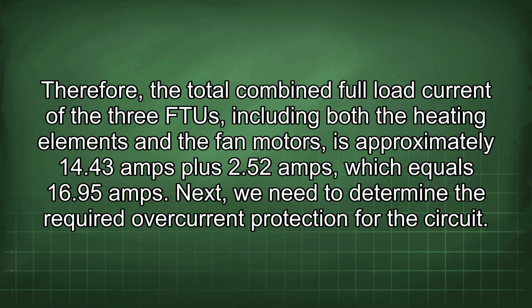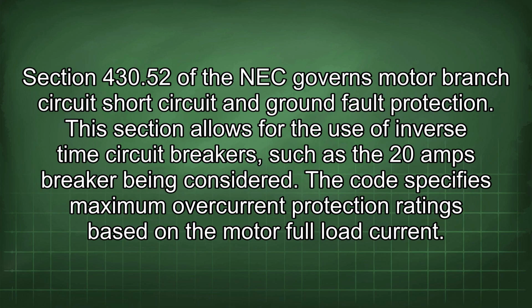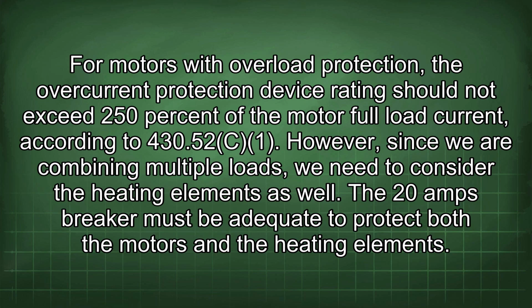Next, we need to determine the required overcurrent protection for the circuit. Section 430.52 of the NEC governs motor branch circuit short circuit and ground fault protection. This section allows for the use of inverse time circuit breakers, such as the 20 amp breaker being considered. The code specifies maximum overcurrent protection ratings based on the motor full load current. For motors with overload protection, the overcurrent protection device rating should not exceed 250% of the motor full load current, according to 430.52. However, since we are combining multiple loads, we need to consider the heating elements as well.